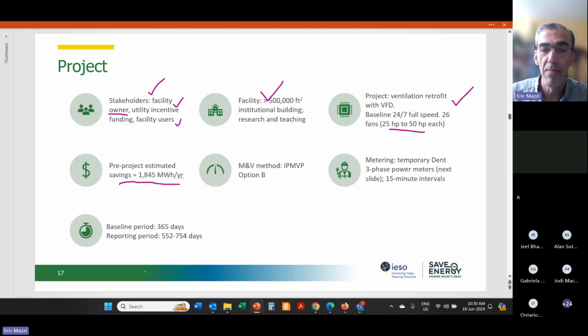The chosen M&V method was a retrofit isolation, called option B in IPMVP terms. Metering was set up with DENT 3-phase power meters. 15-minute intervals were worthwhile. As it turned out, we had a 12-month baseline period, and for certain reasons, the reporting period ended up ranging for some of the fans anywhere from 552 to 754 days. So that's over 2 years for some of the fans, for reasons that I'll mention.